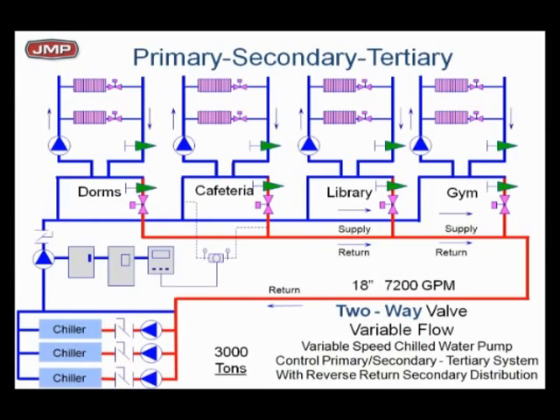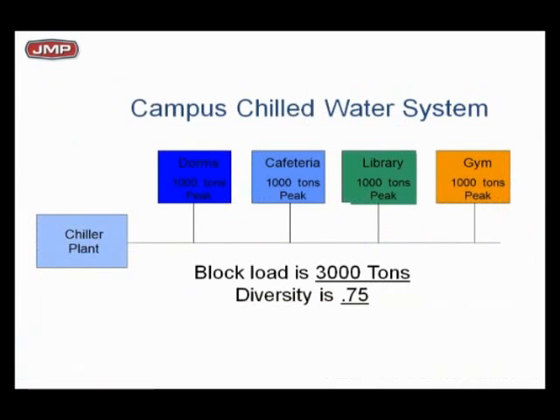Here's a typical campus system. We're going back to the slide we had earlier, remember? Primary secondary at the chillers, primary secondary at the dorms, primary secondary at the gyms. You see how this primary secondary concept fits all over the place. As we work our way through this, you kind of get the idea of a campus system, a central chill water system. You're going to be using block loads. You're going to be using variable flow in the distribution. The chillers themselves may or may not have variable flow. This depends on how you want to design it.